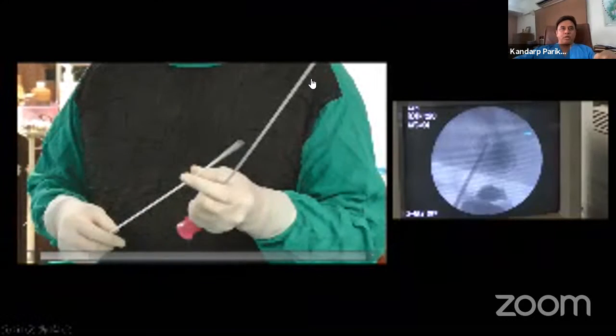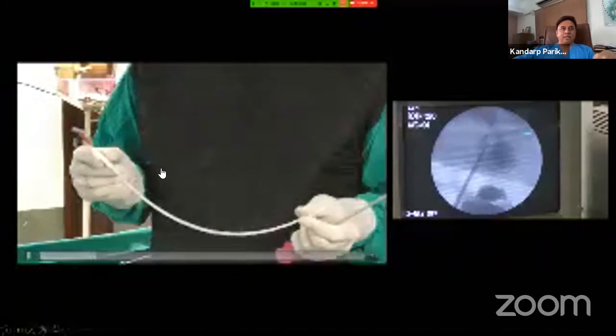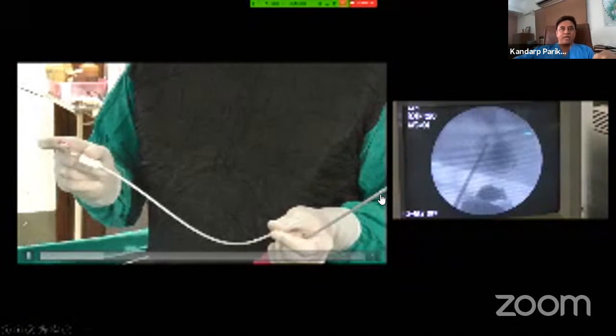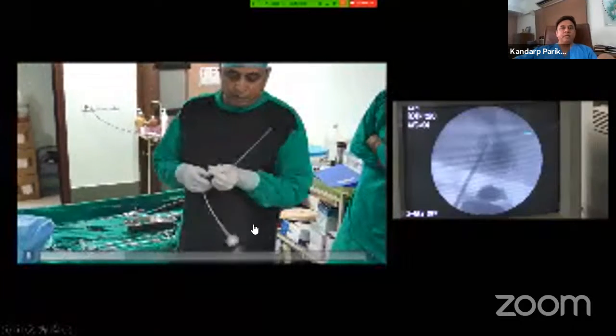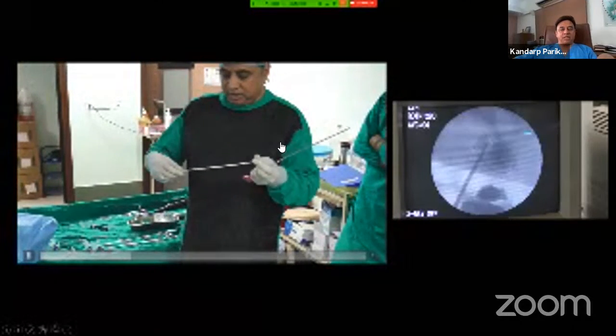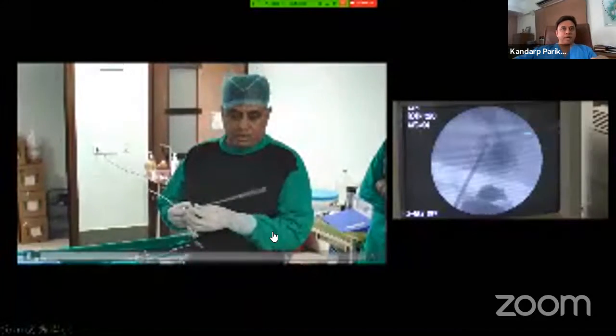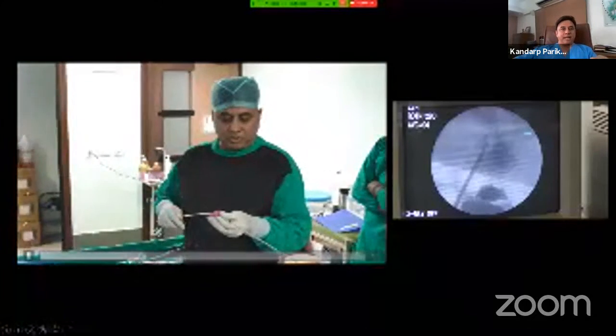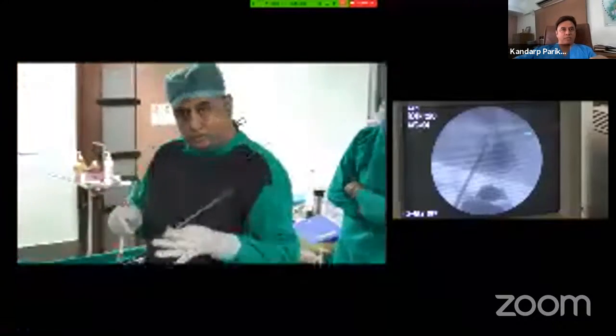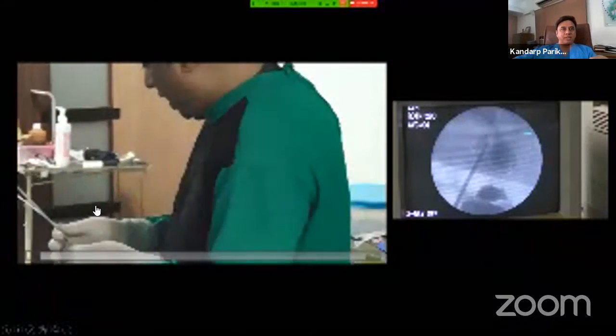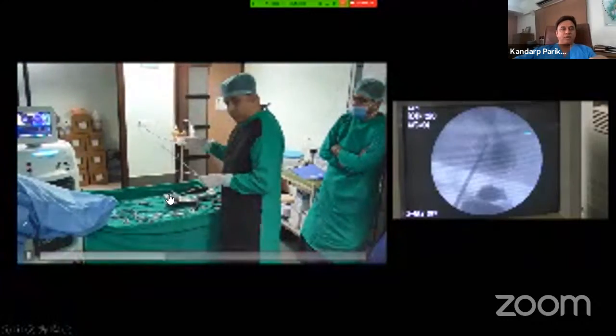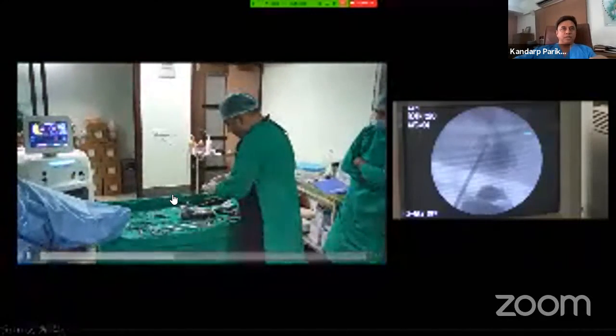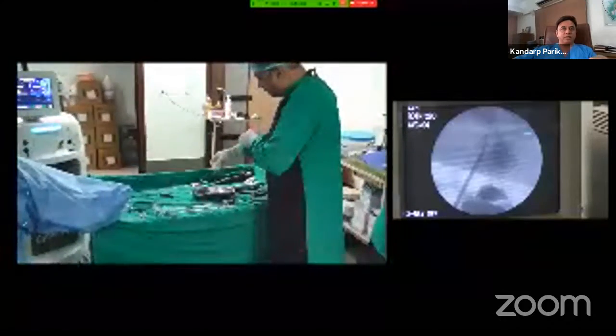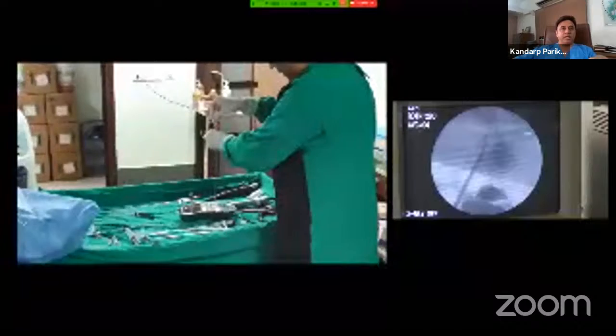It has two parts, an outer part and an inner part. This is a Rocamed ureteral access sheath, which is 10 by 12 French in diameter. The inner part has two lumens, so you can insert a guide wire through it or inject dye through it. Whenever you insert this ureteral access sheath in the patient's ureter, it is necessary that you lubricate it with water, because the outer part of this ureteral access sheath as well as the inner part has a hydrophilic coating. So you can put some water into it and lubricate it.